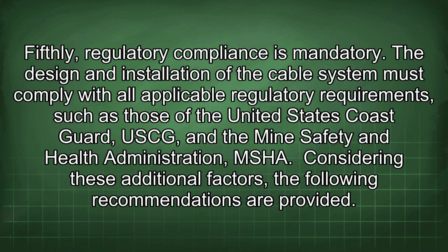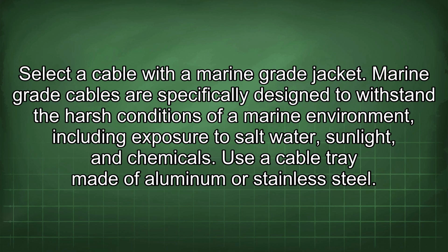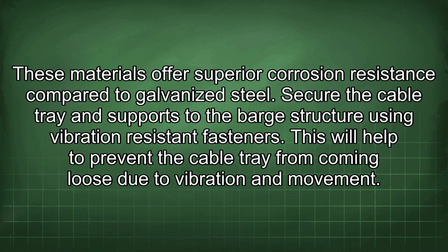The design and installation of the cable system must comply with all applicable regulatory requirements, such as those of the United States Coast Guard, USCG, and the Mine Safety and Health Administration, MSHA. Considering these additional factors, the following recommendations are provided. Select a cable with a marine-grade jacket. Marine-grade cables are specifically designed to withstand the harsh conditions of a marine environment, including exposure to salt water, sunlight, and chemicals. Use a cable tray made of aluminum or stainless steel. These materials offer superior corrosion resistance compared to galvanized steel.